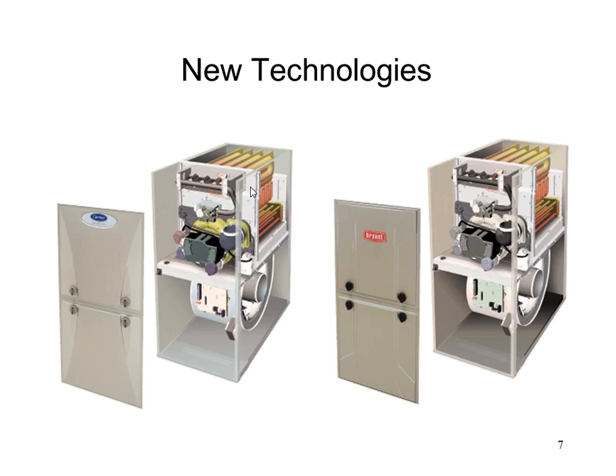You can see it's actually a two-piece design on the door now. So you can take the top door off independently of the bottom door, which we would not have done on past furnaces. And also, when you take the doors off, there are no additional compartments that you have to get into after that. Once you take the doors off on the bottom, you're directly into the blower section. You have access to the circuit board, the thermostat wiring, and all that stuff. If you take the top door off, you are directly inside the burner compartment, and there's no additional enclosures that you need tools to open up. So it is fairly friendly from the service standpoint.